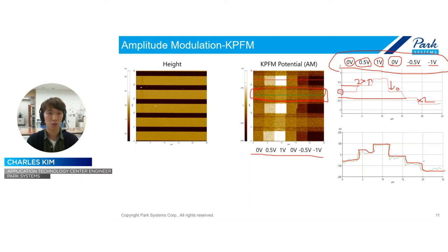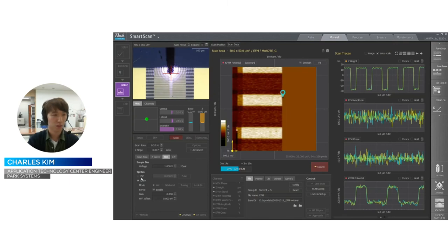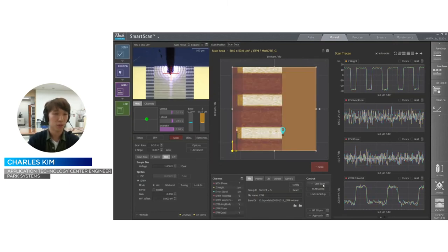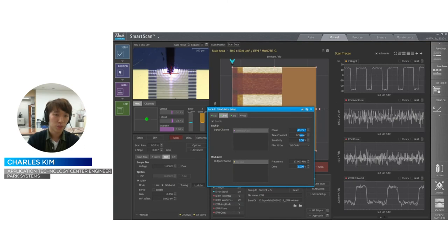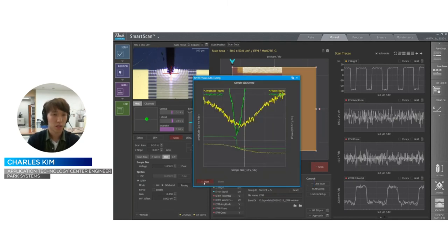So let me show you then how to measure the sideband KPFM. The sideband KPFM is also very simple. To do the sideband KPFM, just change the scanning mode here to the sideband. And also, previously the amplitude modulation KPFM used 17 kHz. But in case of the sideband, we just use a small value of the frequency, for example, between 2 to 5 kHz. So let me use 3 kHz this time. And after that, click the tuning and click the start.